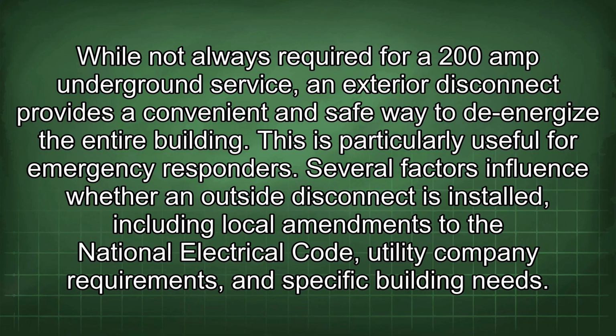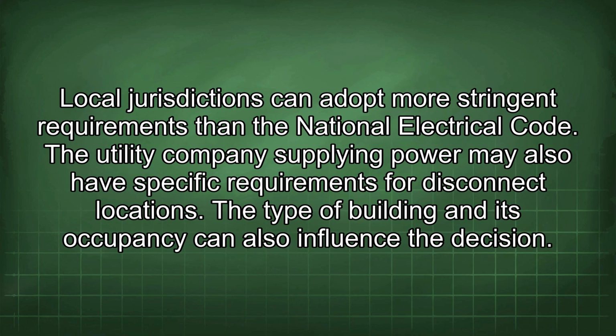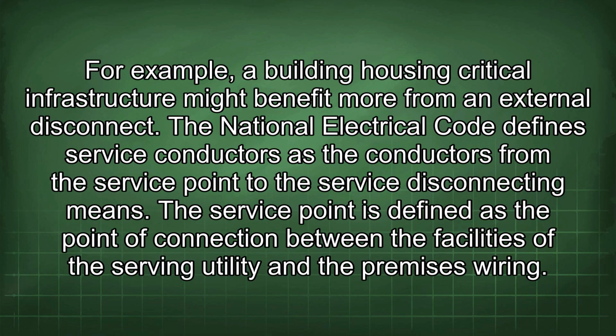Several factors influence whether an outside disconnect is installed, including local amendments to the National Electrical Code, utility company requirements, and specific building needs. Local jurisdictions can adopt more stringent requirements than the National Electrical Code. The utility company supplying power may also have specific requirements for disconnect locations. The type of building and its occupancy can also influence the decision. For example, a building housing critical infrastructure might benefit more from an external disconnect.